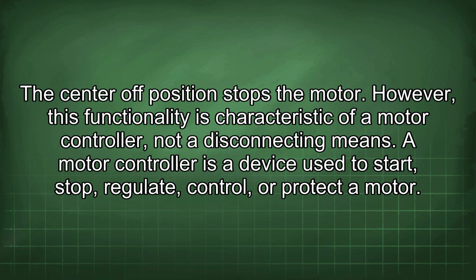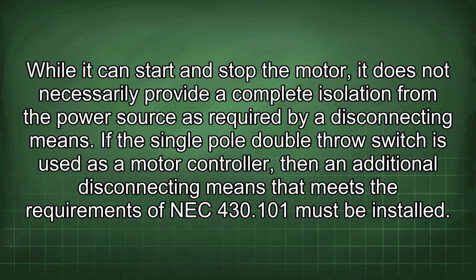A motor controller is a device used to start, stop, regulate, control, or protect a motor. While it can start and stop the motor, it does not necessarily provide a complete isolation from the power source as required by a disconnecting means. If the single-pole double-throw switch is used as a motor controller, then an additional disconnecting means that meets the requirements of NEC 430.101 must be installed.